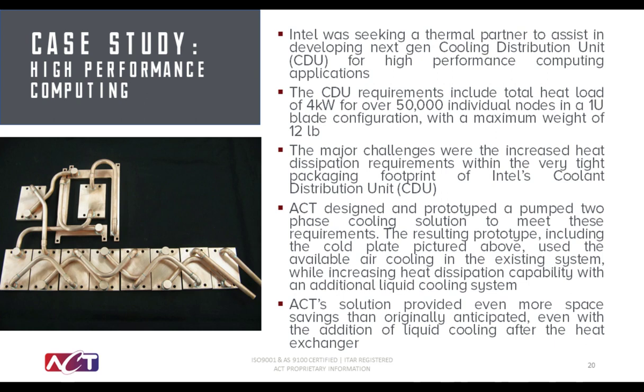The major challenges were the increased heat dissipation requirements within a tight package. ACT utilized a wide array of thermal simulation tools to design and prototype the cold plate you see on the screen. Each of the cold plates is made out of copper, and they're plumbed in series so that every cold plate sees the same flow of fluid. ACT's solution provided even more space savings than Intel originally anticipated, freeing up even more area for the customer's application.